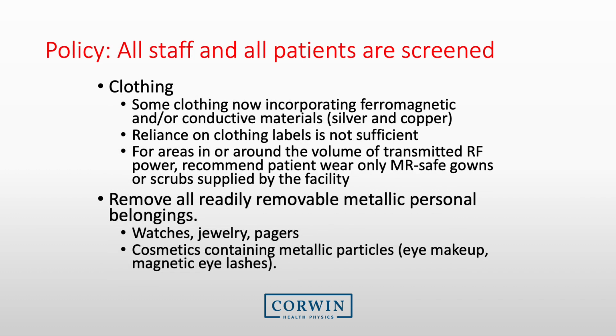When screening the patient, ensure you look at the clothing. Many new outfits have ferromagnetic or conductive materials in them, such as silver or copper. Reliance on the clothing labels is not sufficient, as the quantity of the conductive materials may be small enough to not be listed. All street clothing or workout clothing must be removed due to the new fabrics incorporating metal. Many facilities are simply requesting that all patients disrobe and don an MRI-safe gown or scrub.